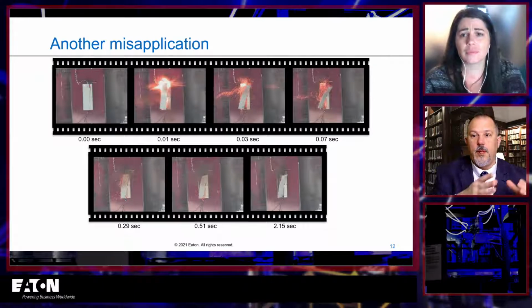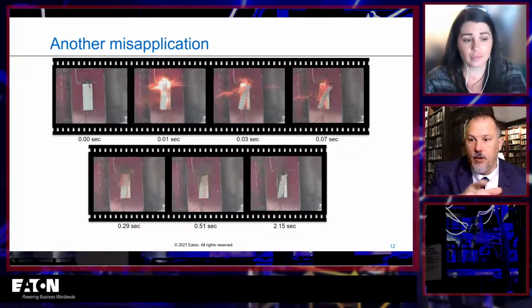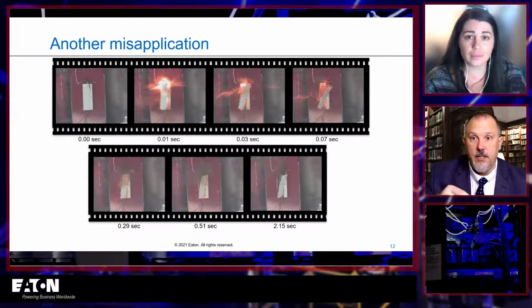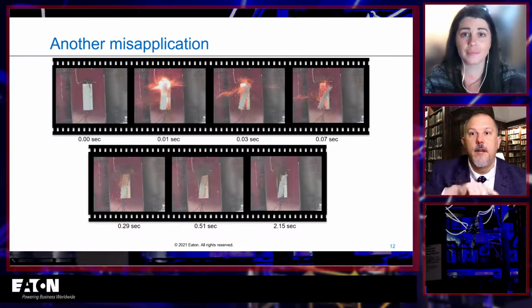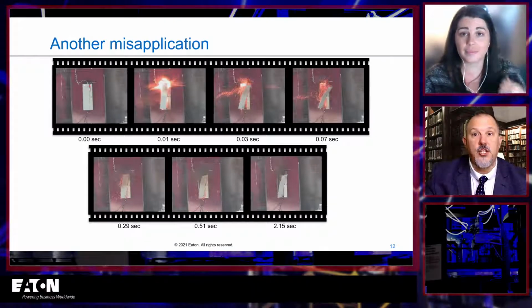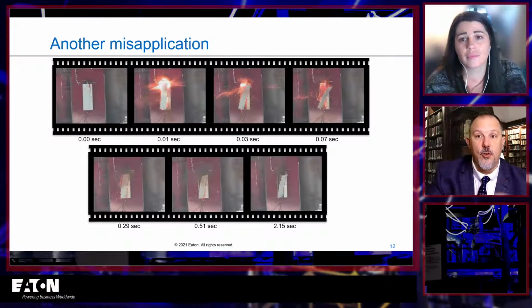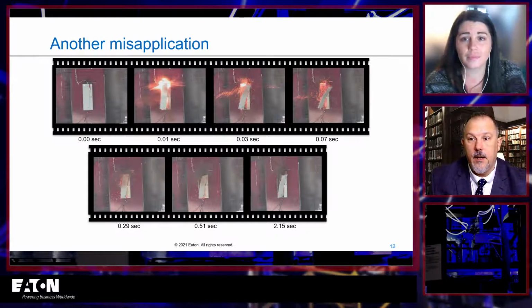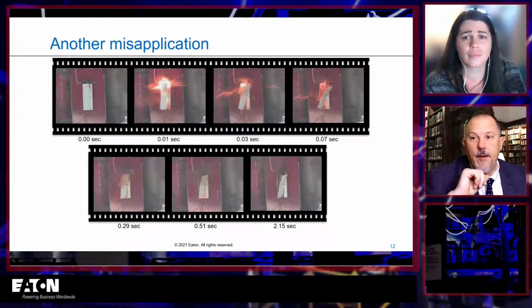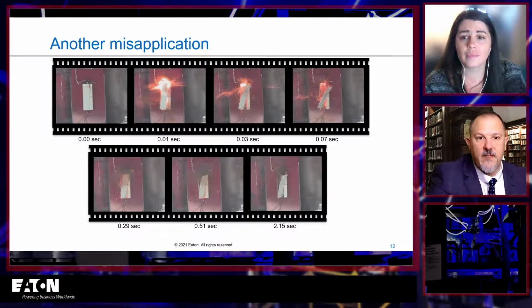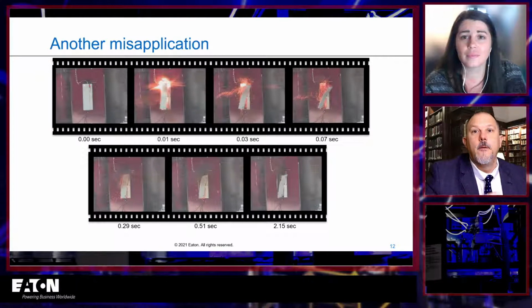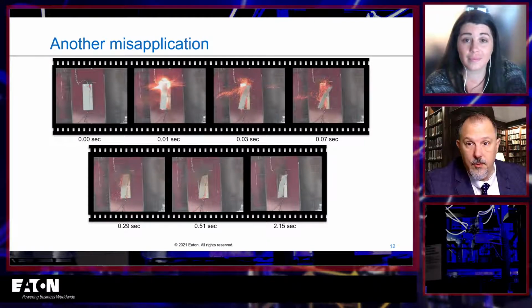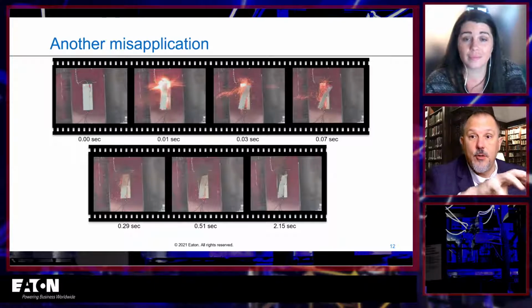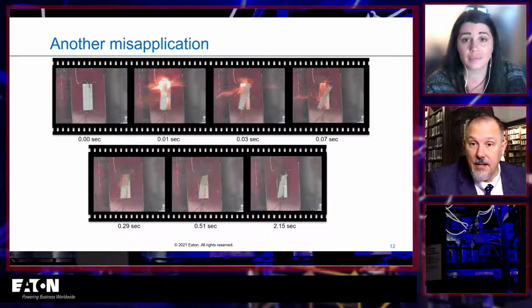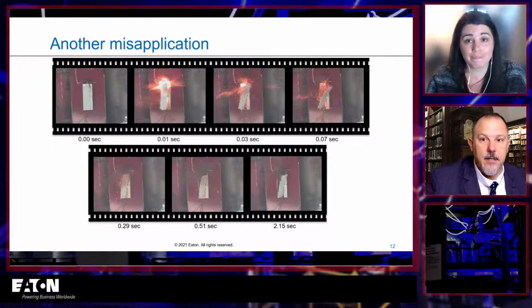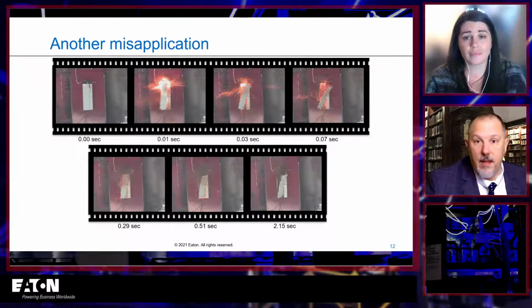So you always will be looking at the available fault current, and Vinny pointed out that peak current will be different because, and I think you have pictures of the waveforms, what current limitation is, and what Vinny is talking about. You'll be telling everybody that information. So when you have a fault inside of a piece of equipment that was high enough to open that breaker or fuse, an evaluation of that equipment after you figure out what the fault was, because 70E tells you need to do an evaluation and an analysis before you do anything with that device.